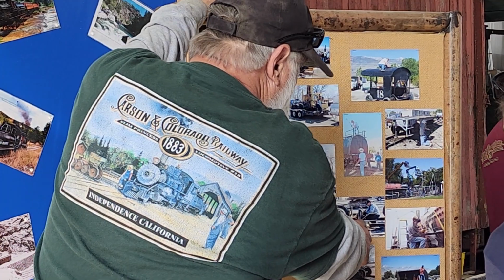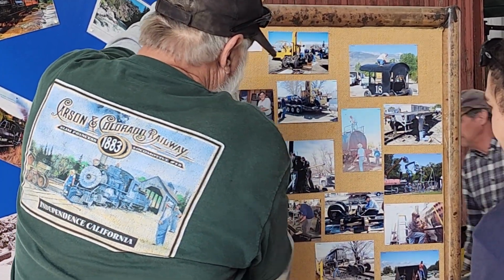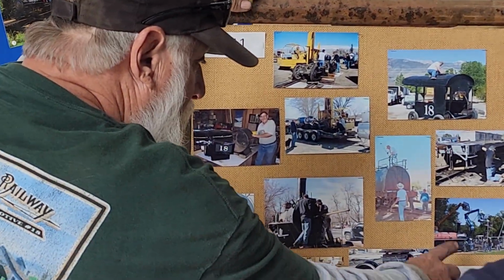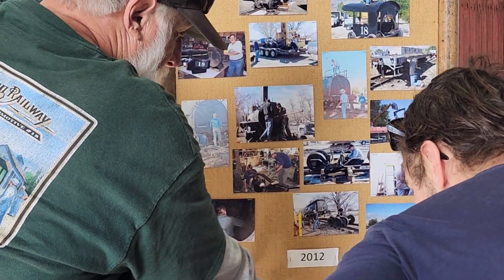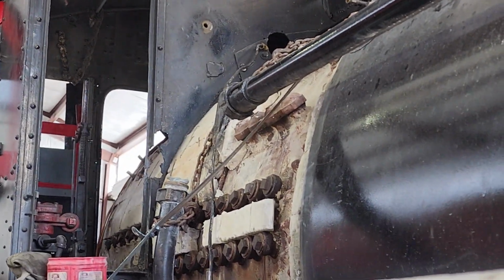Anyway, the front lids came off, and we cleaned all the tubes out. These are the boiler tubes. We removed all the asbestos early on in the project. We found a spot in the boiler shell, right here, that was thinner than UT tested. That's the boiler.